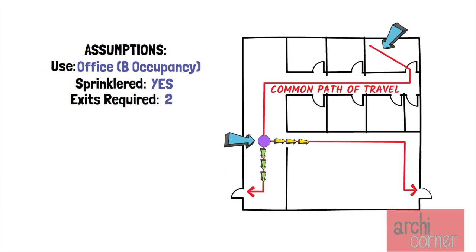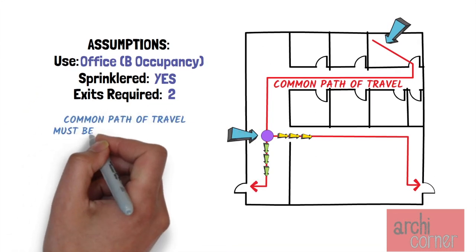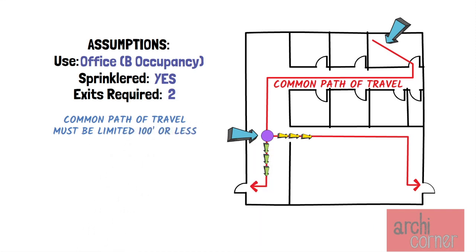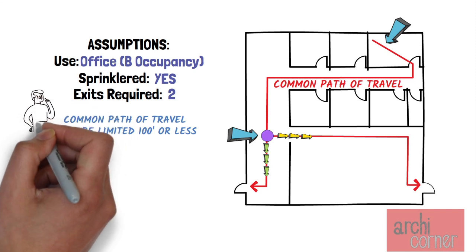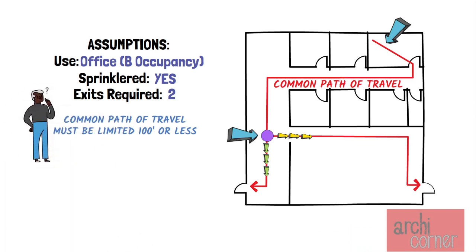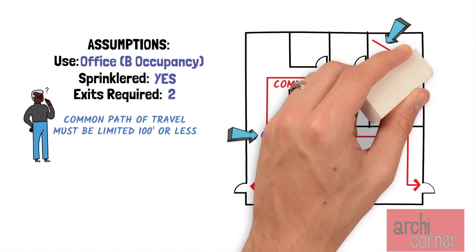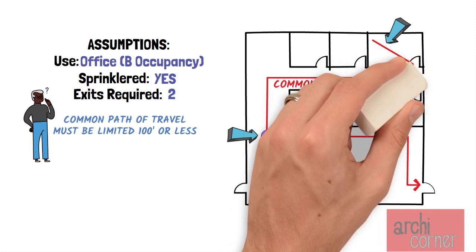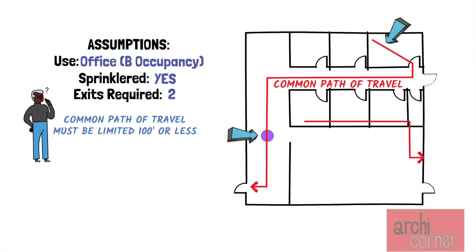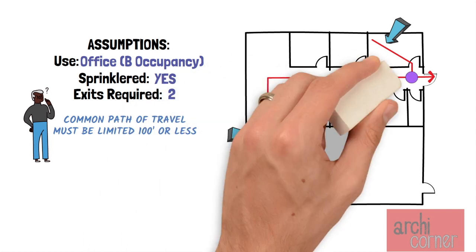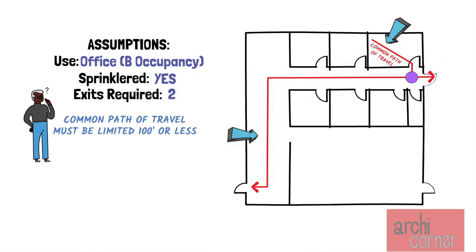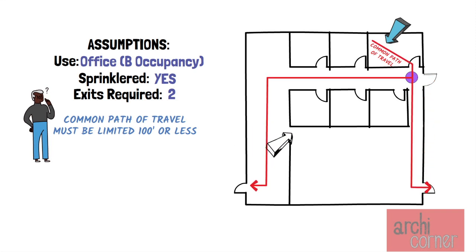Back to our example: the common path of travel must be limited to 100 feet or less. If we exceeded 100 feet for this common path of travel, we would have to modify the plan to reduce it. One way of doing this would be to add a door, which would significantly reduce the common path of travel. Another solution could be to create a hallway providing access to the original second exit. There may be multiple ways to provide a solution.